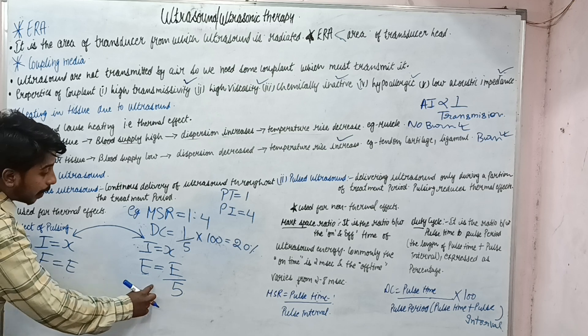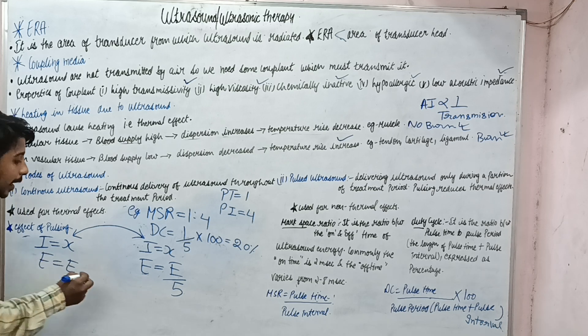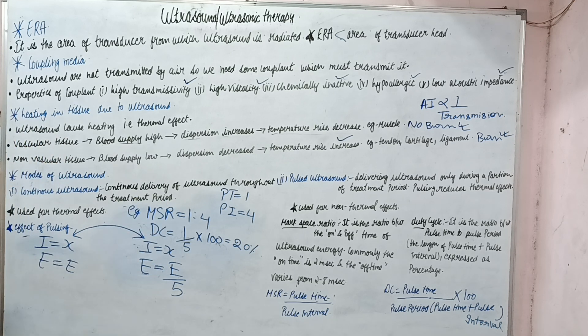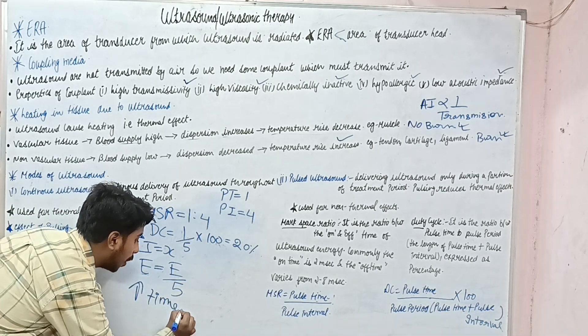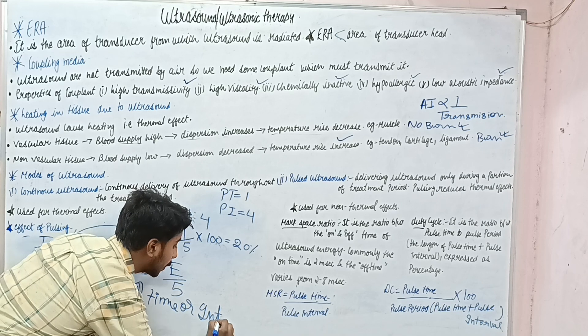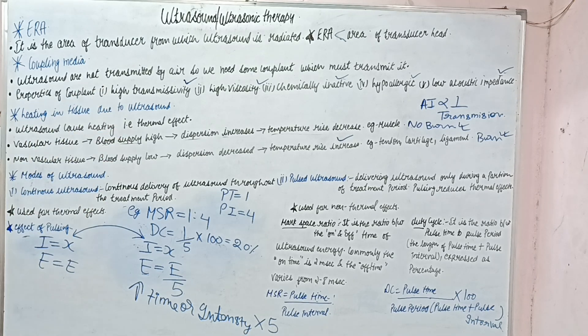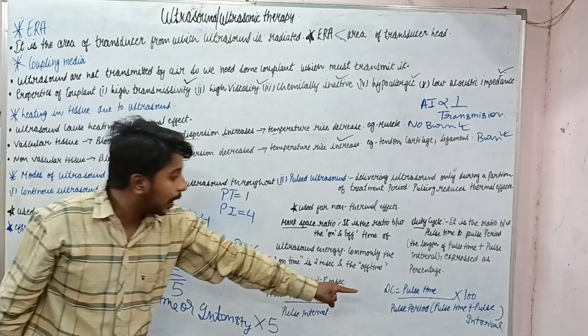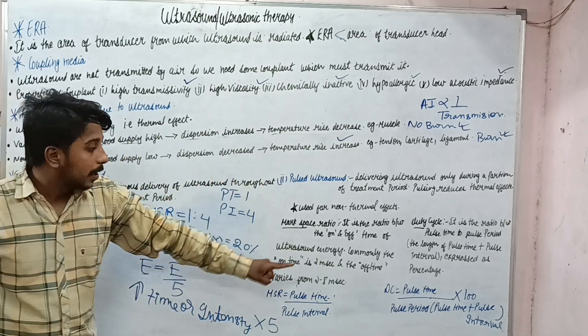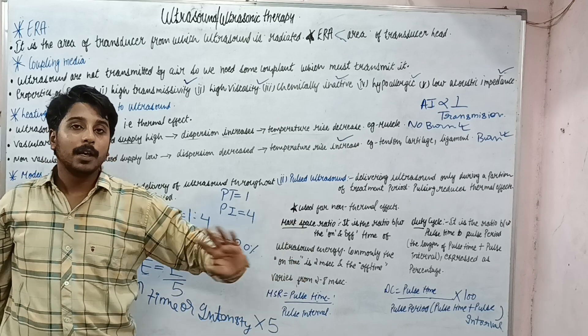To deliver the same energy E in pulsed mode as in continuous mode, we can either increase the intensity by 5 times or increase the treatment time by 5 times. This means higher intensities can be applied safely in pulsed mode. At the same energy, the continuous mode would have a harmful thermal effect on tissue, but pulsed mode allows safe delivery of higher intensity.